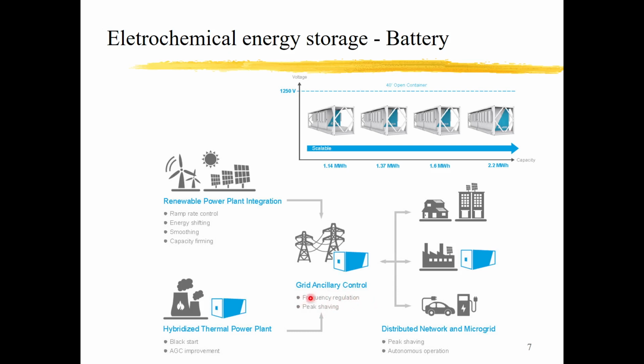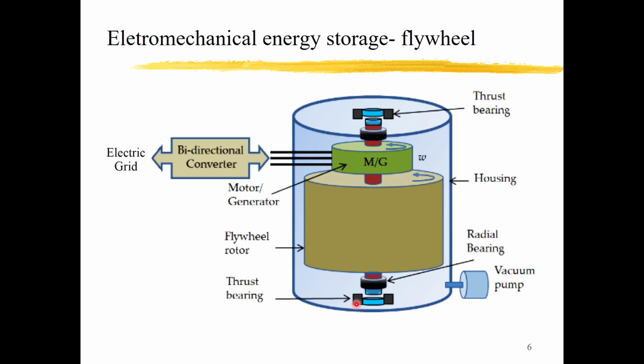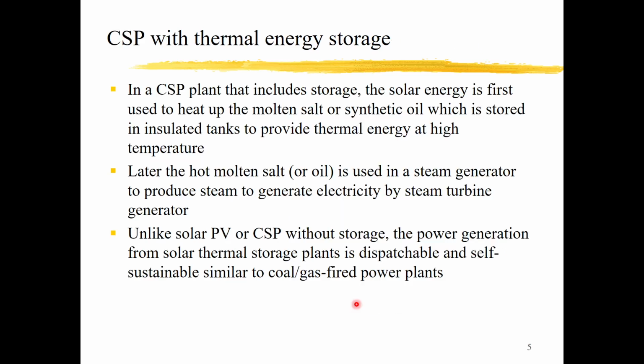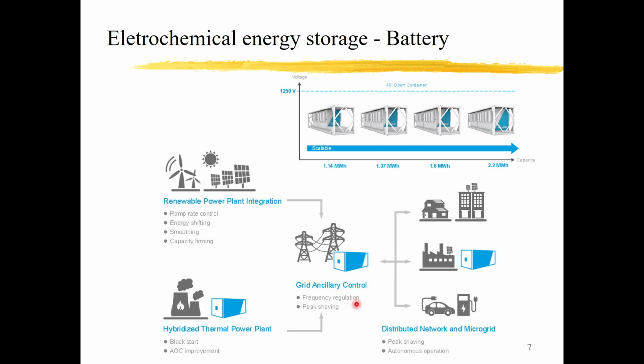And how can we achieve the frequency regulation? Again, by the energy storage. Because the frequency variation is very quick, only the electrochemical energy storage can support this function. The electromechanical system's time constant is very large compared to the battery. And for the thermal energy system, again, the time constant is very high, so it cannot respond so fast. Only the electrochemical energy storage can do that.